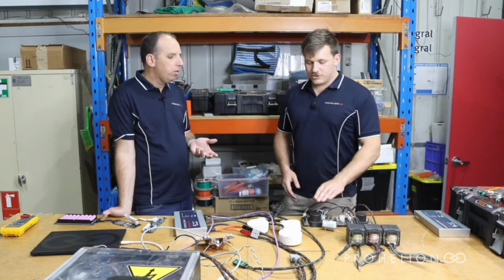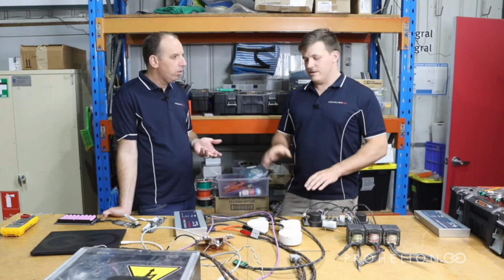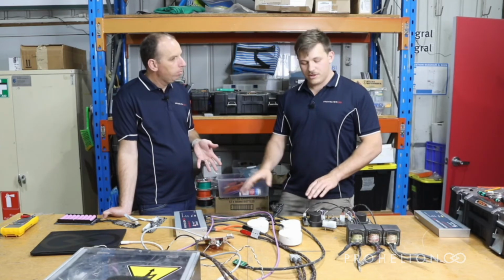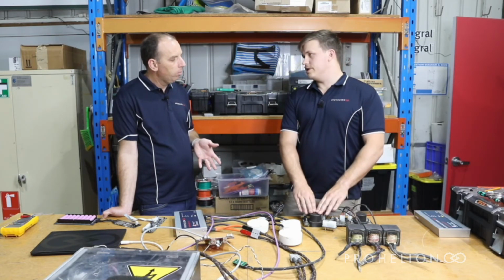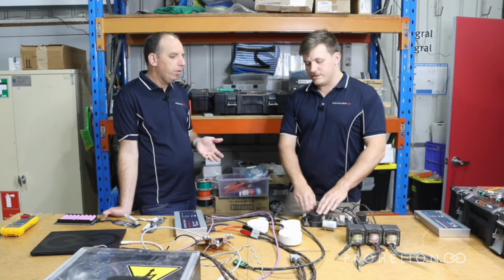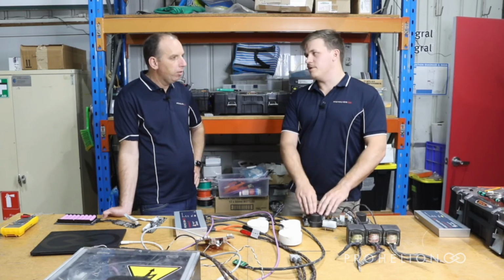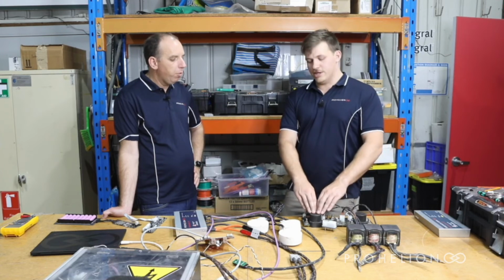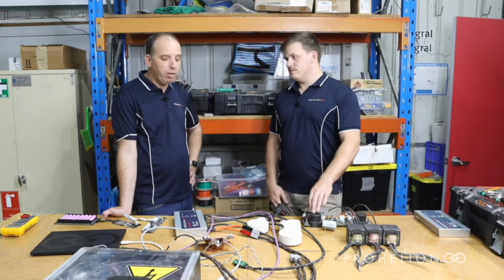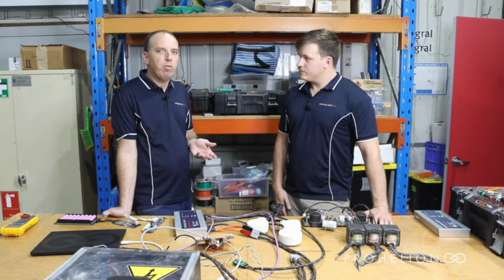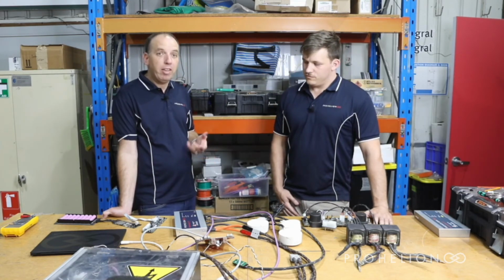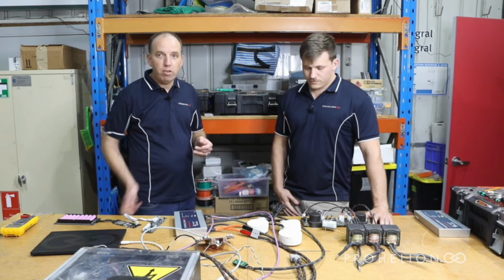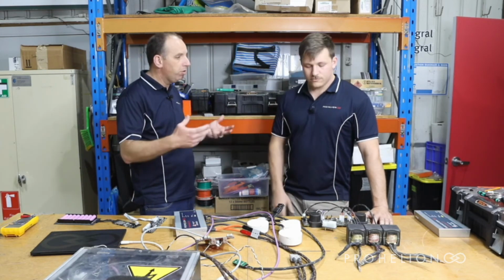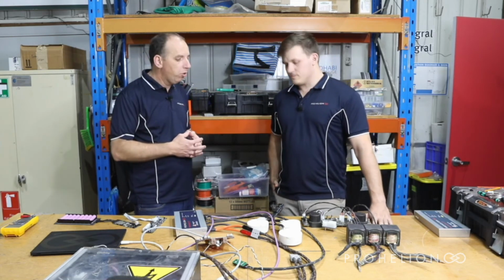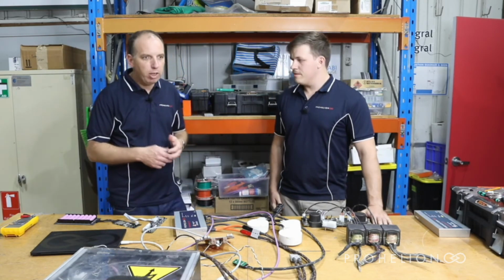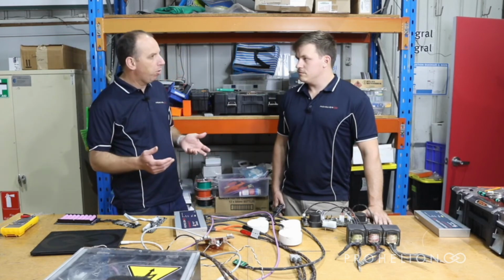Exactly. So you're just trying to limit that inrush current, which can either damage the connected equipment or damage your contactor, because you can weld the contactors if you don't have precharge. And that is typically the failure case that you'll see without precharge, which can be quite a dangerous scenario. So it's definitely worth doing. All of the settings that Sam's just talked about are configured through Profinity, and they are configurable to set the different ranges and the time periods that things are going to occur over and so on. We do have some recommended values in there, but if you wanted to change anything, that is possible.